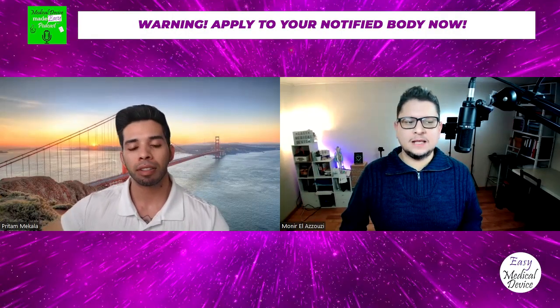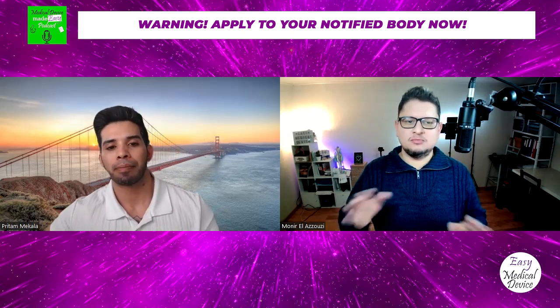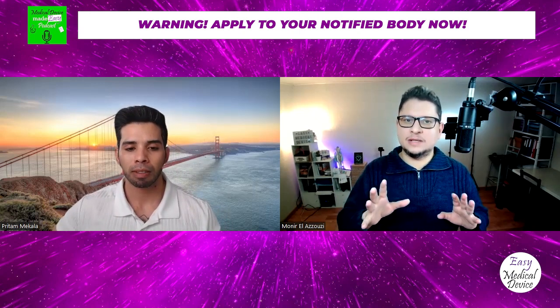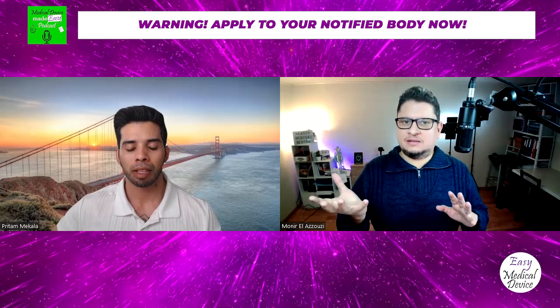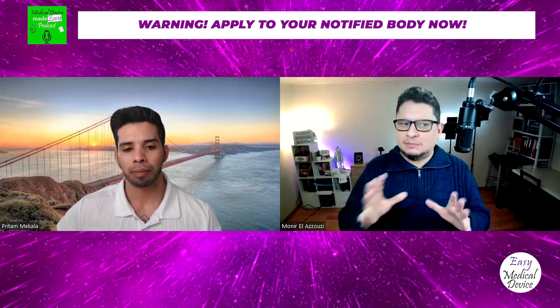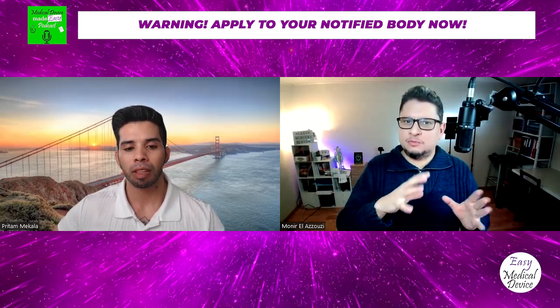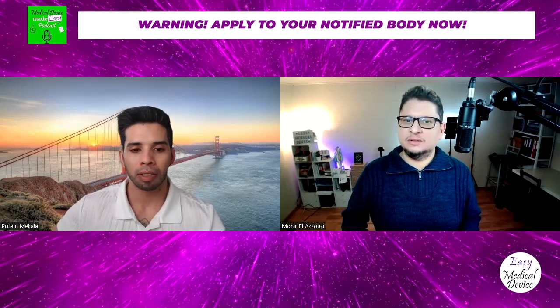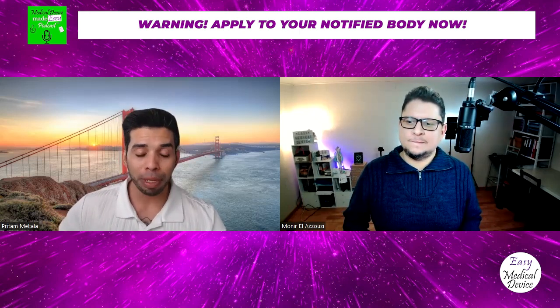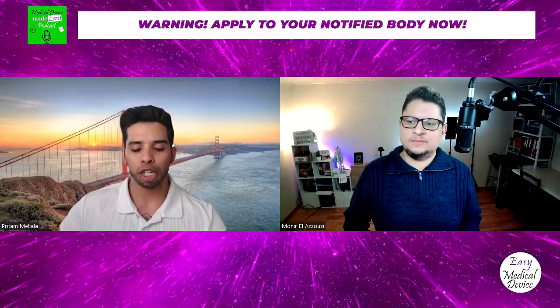Great. And just to compare to what is happening in the US, can we say this structured dialogue is comparable? I'm not sure it's the same, but as the Q-Sub or pre-sub for 510(k), for example? It would be, yes. But I think discussions would differ based on the topic as well. But it is along the lines of that.